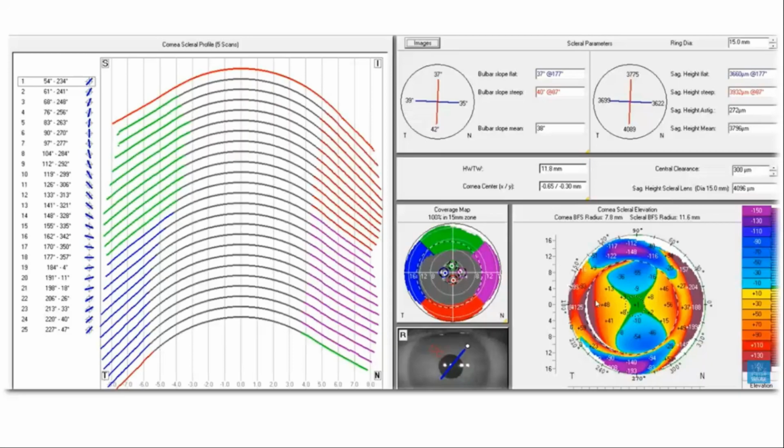For example, we don't have the cataract densitometry. Yes, sir, we don't have. When I clicked on the contact lens fitting option, this screen didn't show up, so I thought it must be present in AXL. No, no, AXL has nothing to do with it. It is available on the normal Pentacam also, but you have to purchase that optional software.